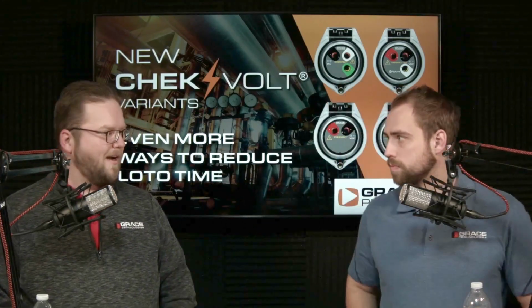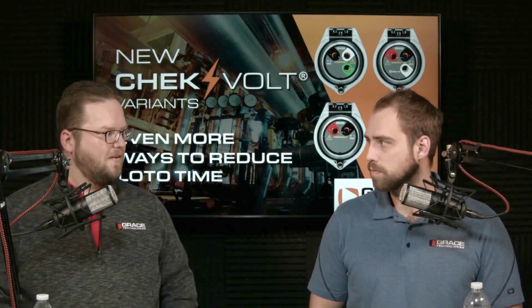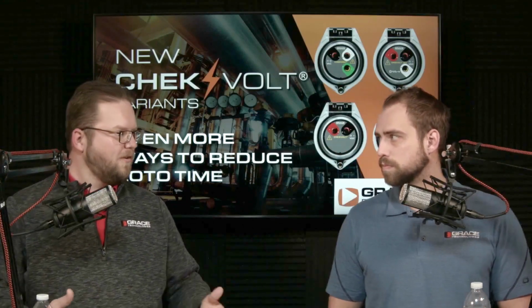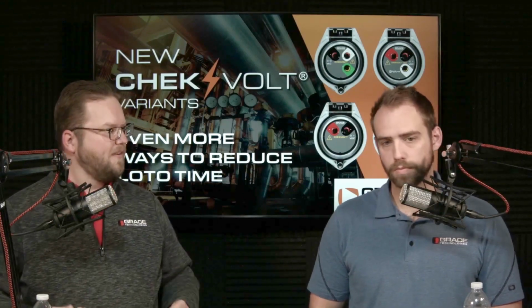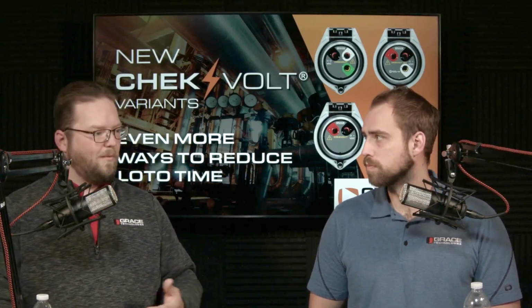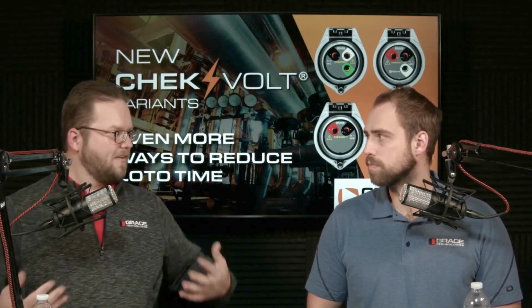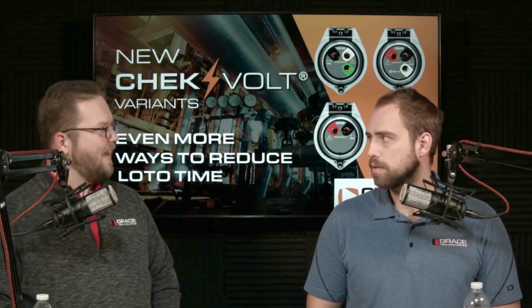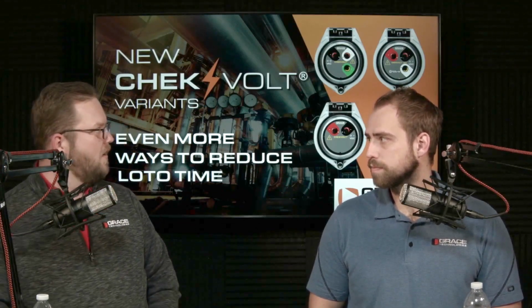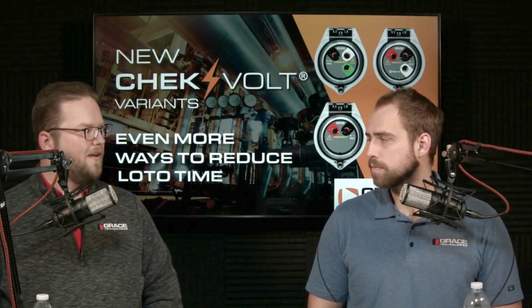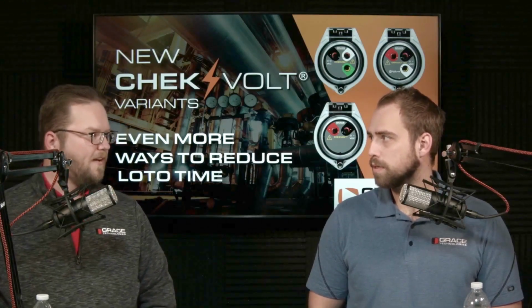In solar applications, we have combiner boxes where at the end of the array there's 1500 volts DC, and they didn't want to have to buy special equipment to test absence of voltage on that. They wanted to do it from outside so they didn't have to suit up in safety PPE. So we developed that one. Do you want to explain how we accomplish being able to use a standard meter to test absence of voltage on that?